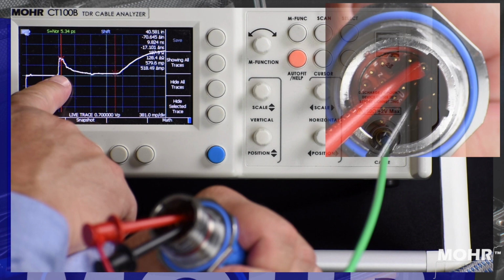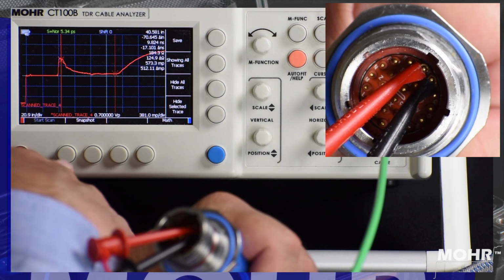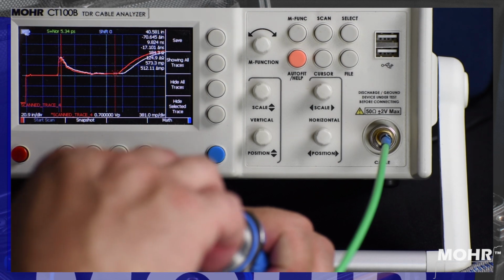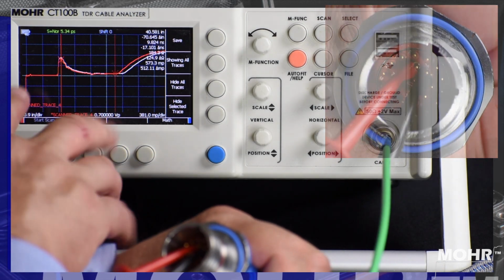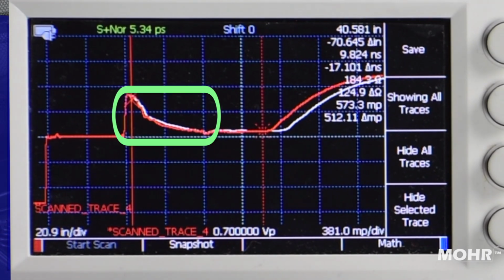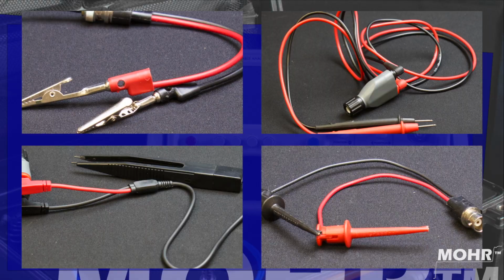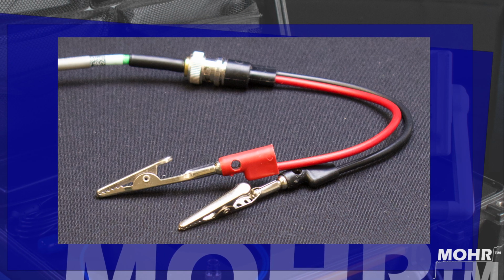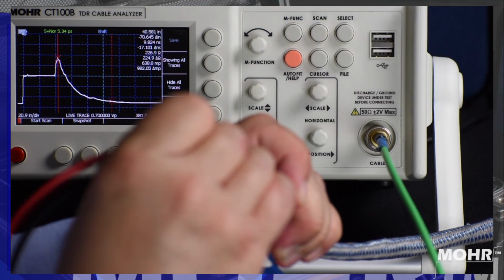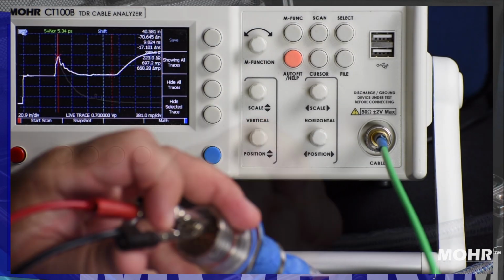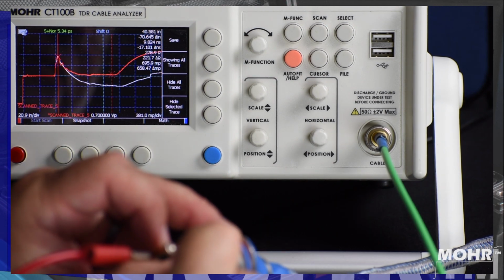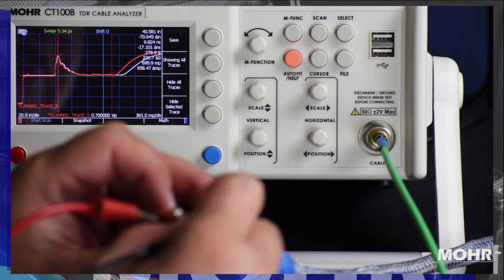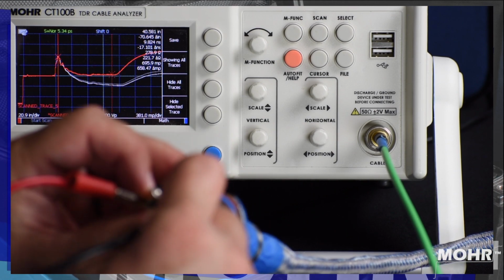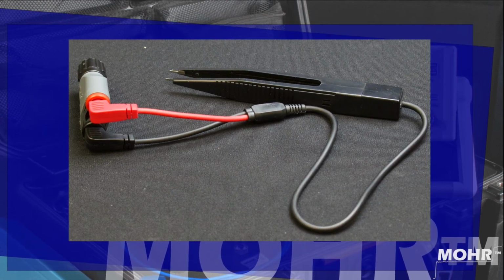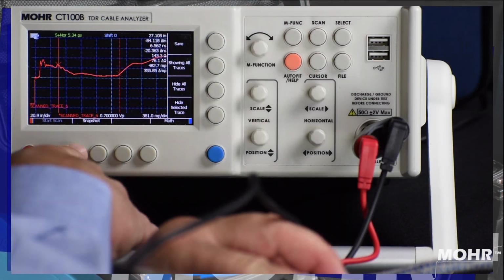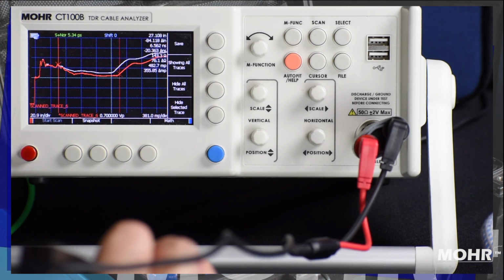The hooks were able to connect to these pins, but they were hard to get on and stay on. If the pins would have been larger or smaller, it might not have worked. We can see the comparative trace, and it's quite distorted. Even worse with the alligator clips, as they wanted to short against each other, the plug assembly itself or the neighboring pins. And the comparative trace is even more distorted than we had with the hook probes. Using the tweezers as pins gave us a very distorted trace on the other side, where the hooks and alligator clips couldn't go.